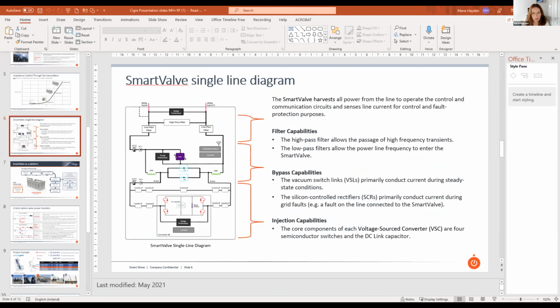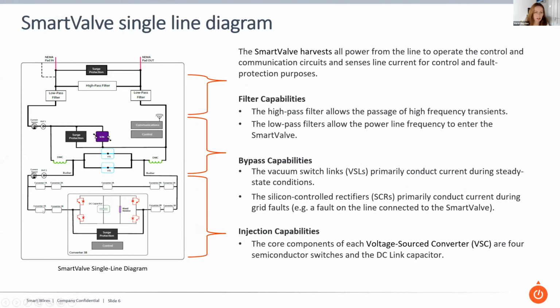Geoff, I think you have a question. Yes, it was just on the bypass you had for the whole device. Do you have submodule bypasses as well? We do, yes. In the latest version of the technology, what you see here, hopefully you can see my screen, is a single line diagram representation of the smart valve. In fact, it's not just one voltage source converter, it's multiple converters. This is actually the 3600 amp version, so we run two 1800 amp paths in parallel. In the version that we're releasing in January, we run 10 converters in series, so we get double the voltage injection. It's only up to 1800 amps.